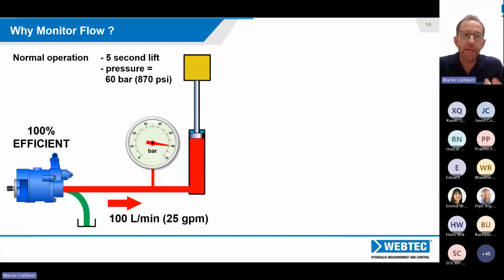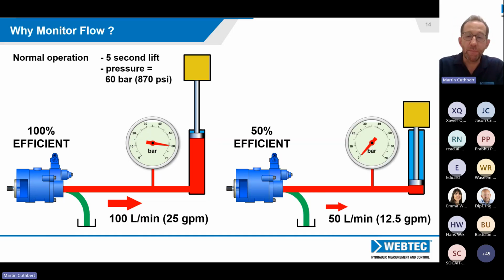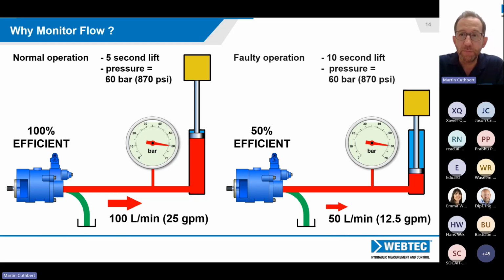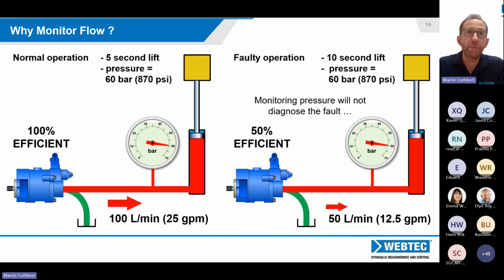If we put that same gauge onto the circuit of a pump that's only 50% efficient and run it, we'd see it's still running at 60 bar, because it's still got the same load to lift. The pipework's identical, and the only difference is the weight takes about 10 seconds to lift rather than 5. So in terms of monitoring pressure, that won't diagnose the fault for you.